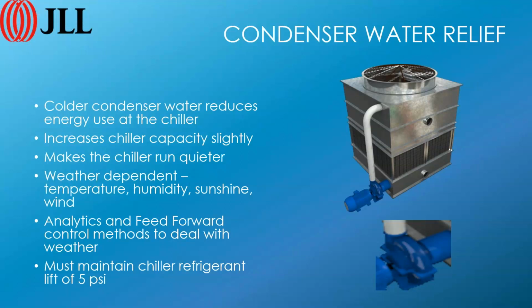And if the power plant use went down under the same cooling load, then you made a good decision, so let's drop it down another degree. And if the total power plant use went up, you made a bad decision, and it's time to go back up. That will happen all day long. The tower water temperature will reset up and down all day long as the sun goes up in the morning, as clouds come and go, as the temperature and humidity change, as it rains, and if any wind comes up, all those things that affect cooling tower operation. As those things make the tower more efficient or less efficient, you're able to take advantage of that and run condenser water temperatures up and down.